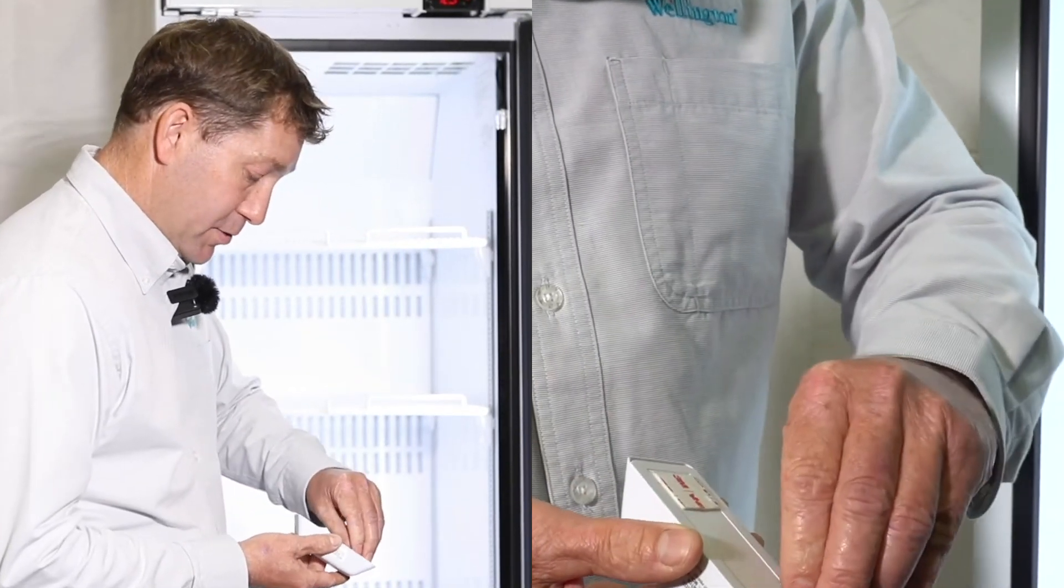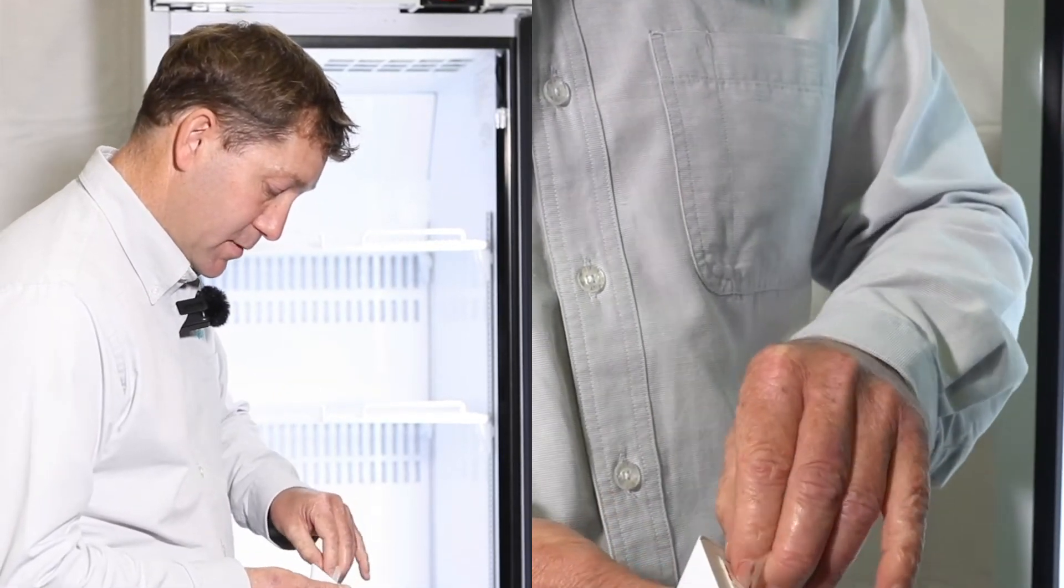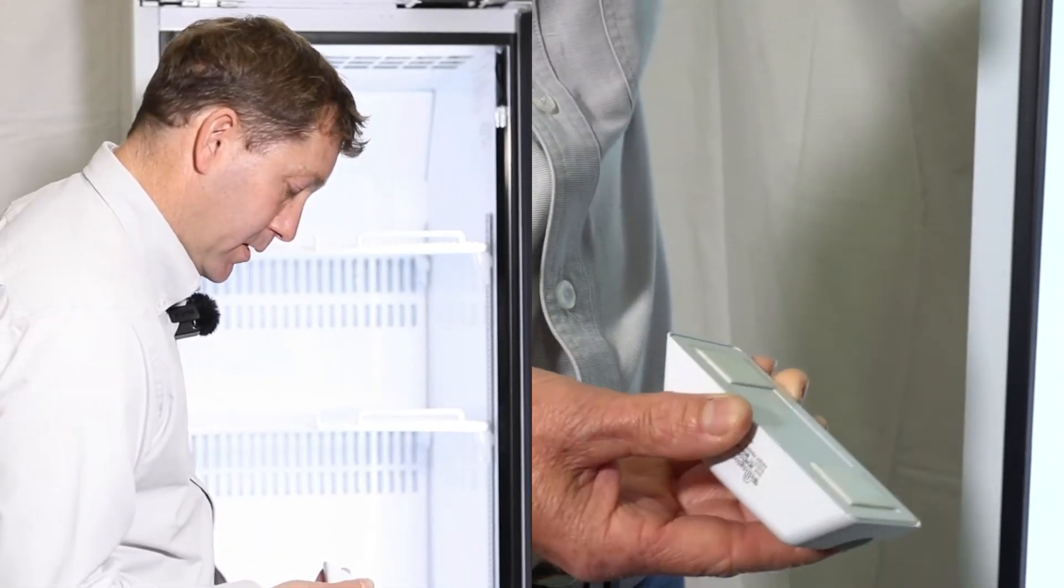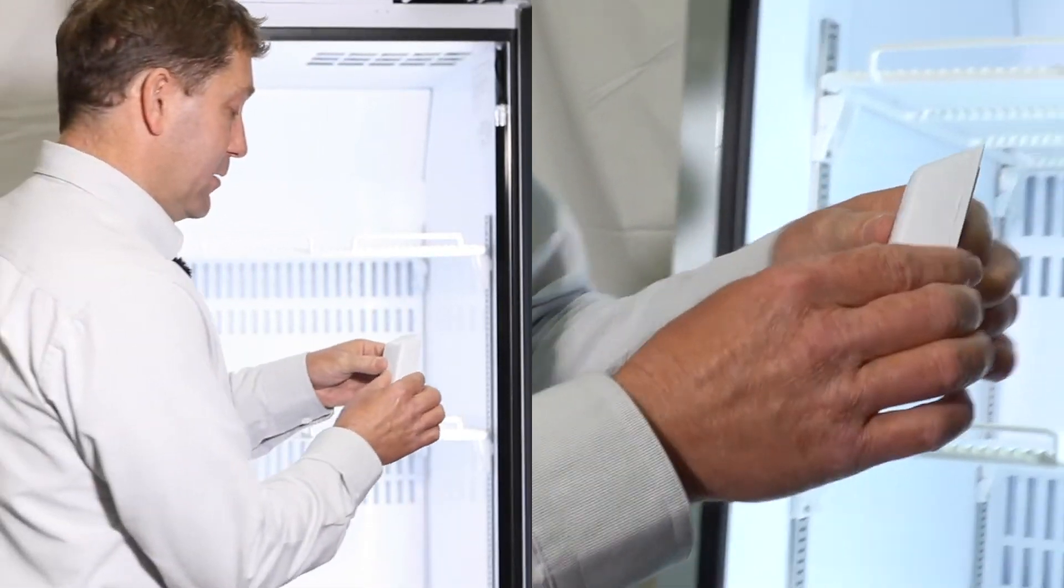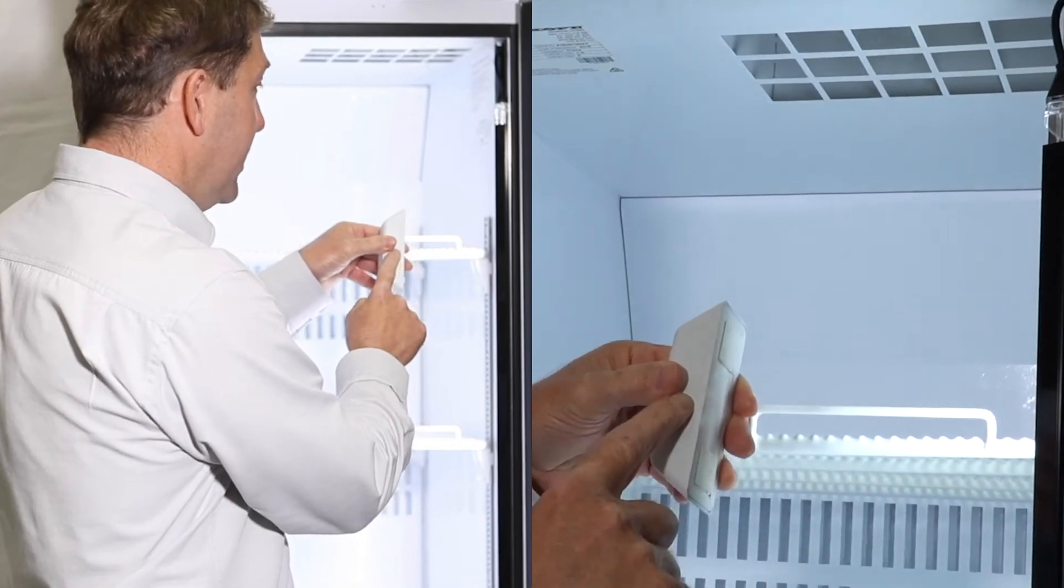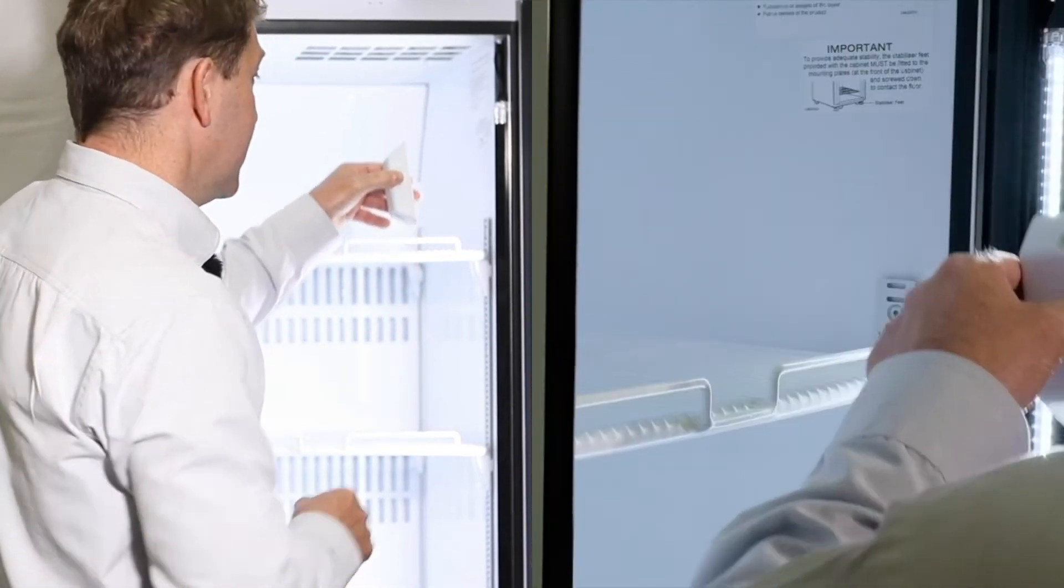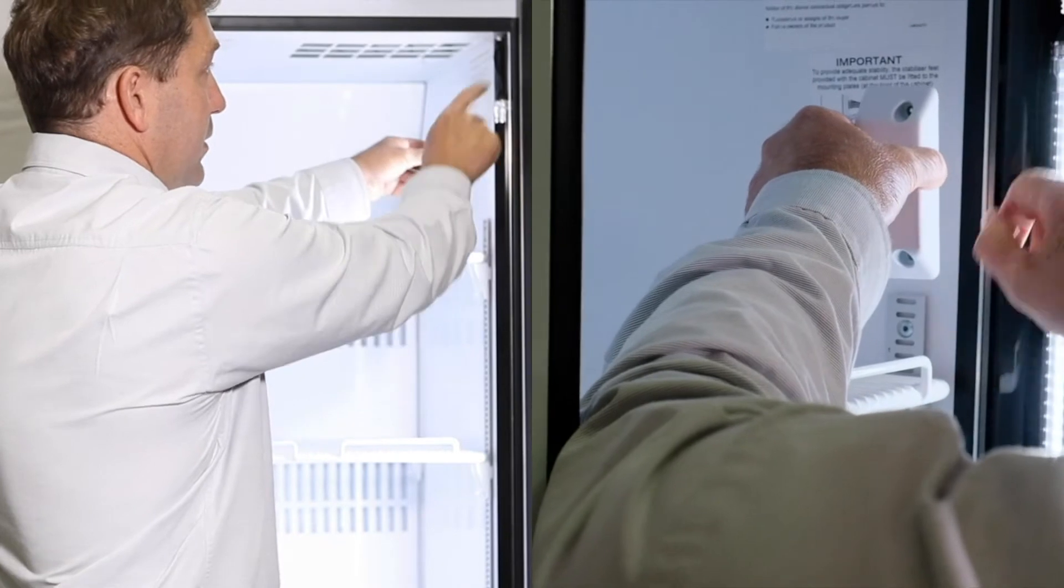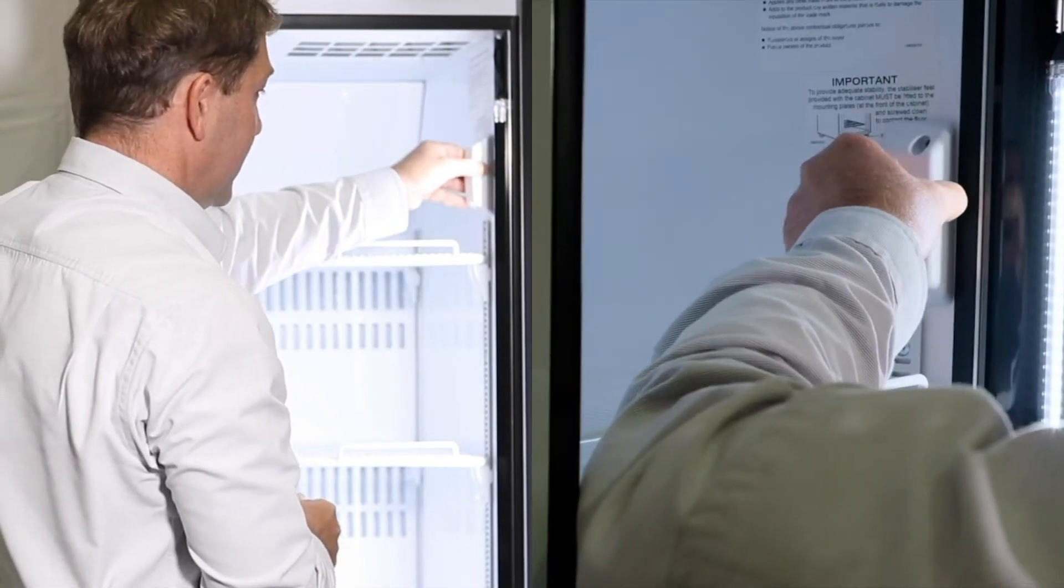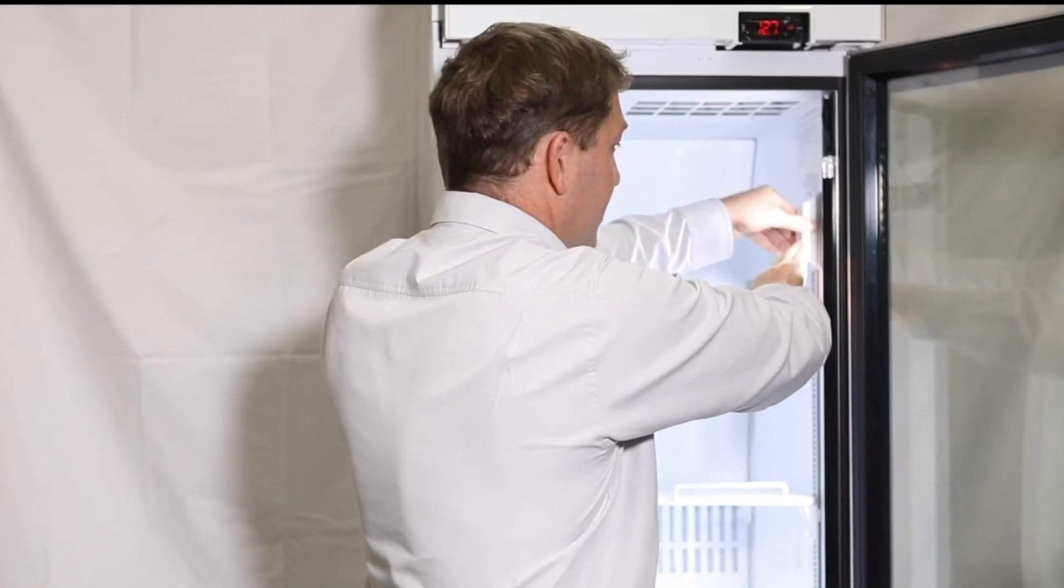Now what we're going to do is we're going to mount this and we're going to remove the sticky pads so it sticks to the side of the cooler. Now it's important how deep into the cooler it is mounted. The front of the monitor here must be within seven centimeters of the front edge of the cooler. So we're going to mount it as far forward as possible here and press firmly.